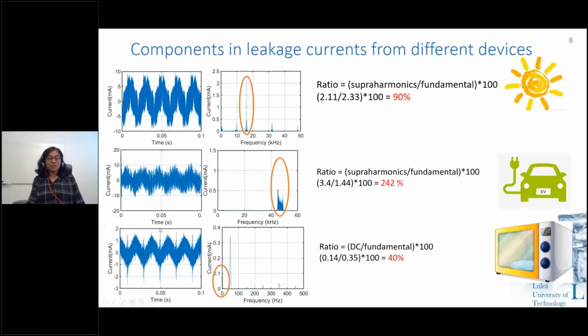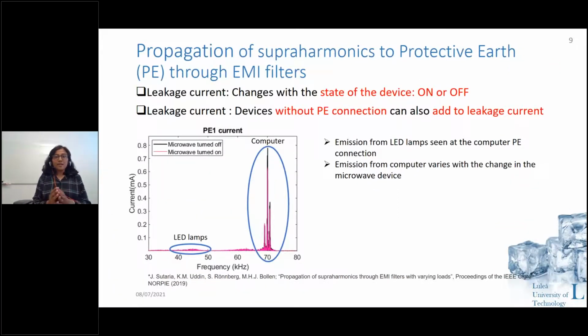In this case, we used a microwave and did a measurement, and we saw that there is a DC component even in the time domain waveform that we can see. This DC component was around 40% of the fundamental component. So this is how the leakage current looks, and this is why there was a concern about how the waveform composition of leakage current impacts the RCDs. Also, this is something about how the leakage current changes with the connection of the devices and how they pass through the EMI filters.